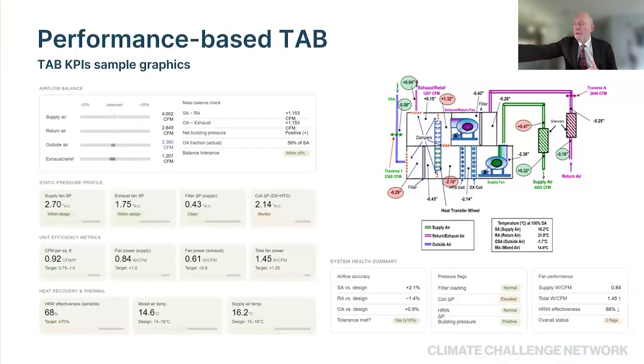What Mark has done here is colored in green circles. Do you see that? The things that are reasonable. So the exhaust relief air going to atmosphere at plus 0.04, that's reasonable. The outside air intake is reasonable. And at the other end of the system, the total external static pressure, the supply in the green, like 0.32, is a pretty good supply static that can feed the variable volume boxes or whatever's downstream. And the minus 0.16 is okay. So those green ones are good.